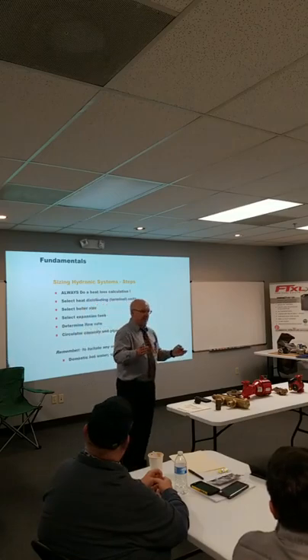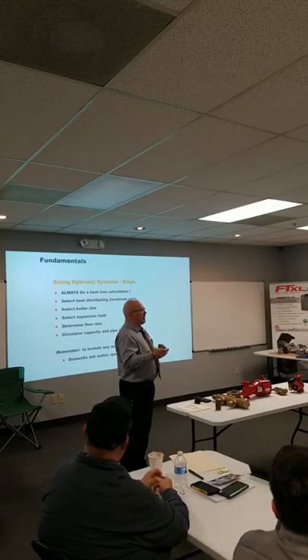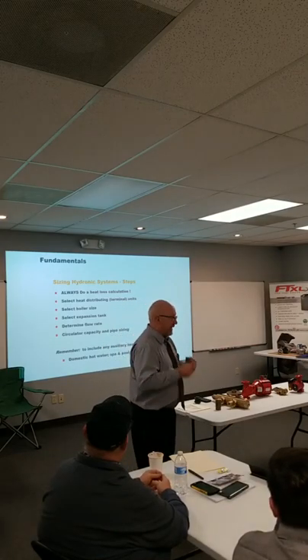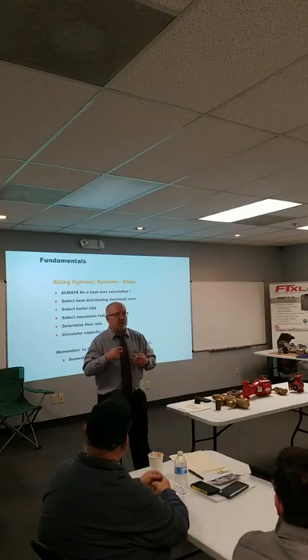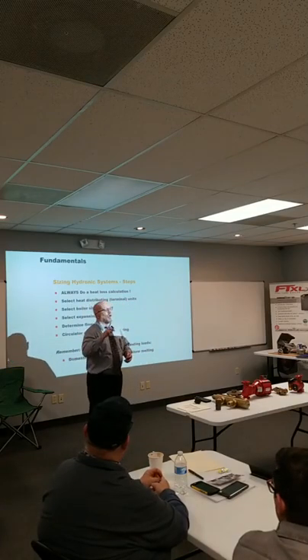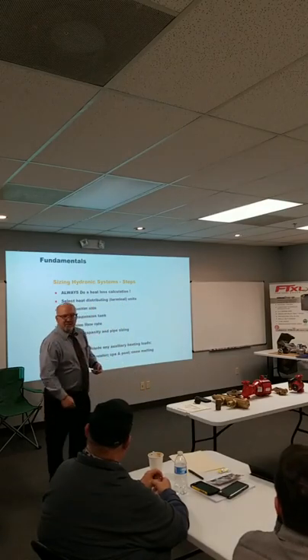And what kills anything? Cycle rates. You oversize a condensing boiler, you're still going to short cycle it. And there's less water content, so they cycle a lot more than even a regular boiler. So I still say that I would rather undersize a condensing boiler than oversize one. And we'll talk about it. We're going to talk about a lot. We're going to be here for 4 hours.